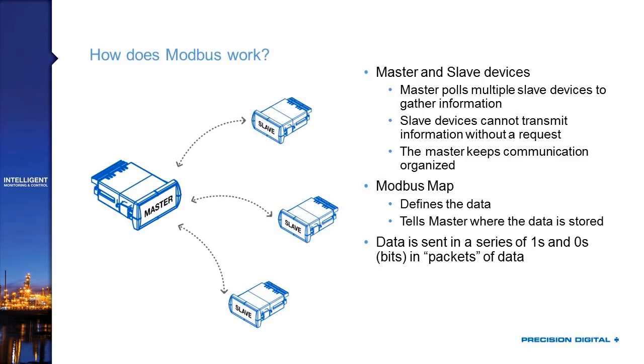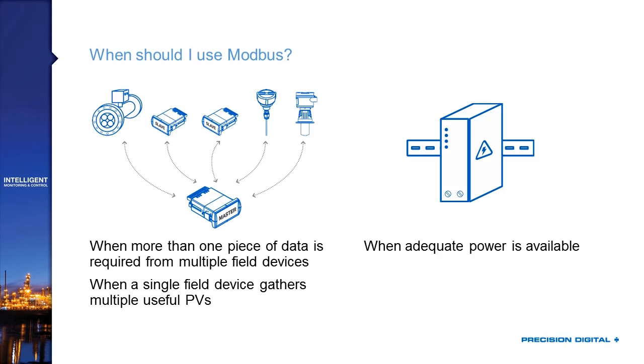When do you actually want to use Modbus? Why is it useful? Modbus really functions well when you have more than one piece of data passing through a device — either because a field device has multiple pieces of information you want to extract, or because you have many field devices and want to bring them all back to one location. For example, a multivariable level transmitter might have a top level, an oil-water interface level, and a temperature. To get all three via 4-20 mA you'd need three loops, but with Modbus you just ask for different registers.